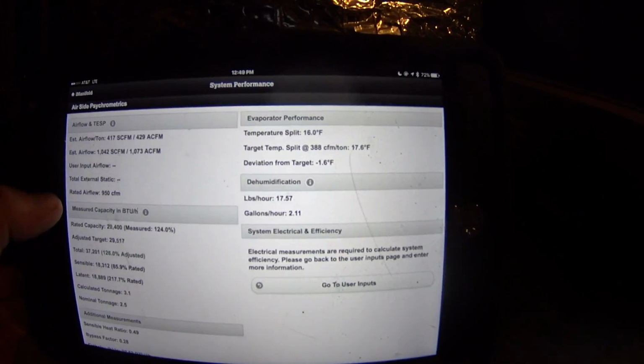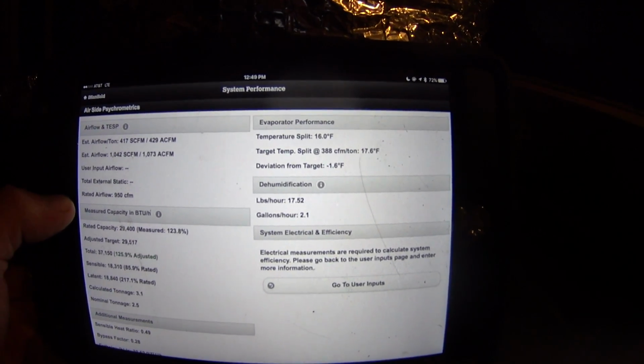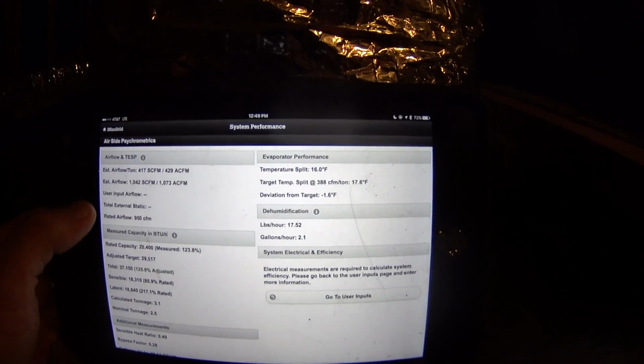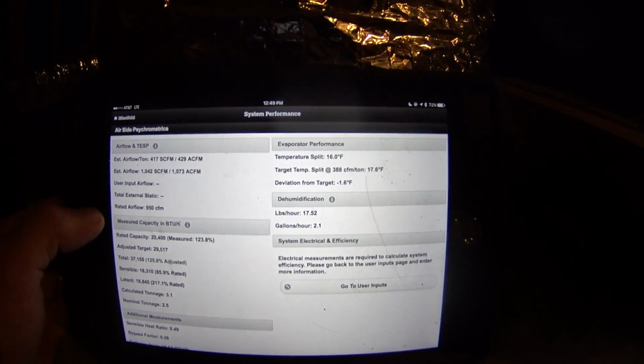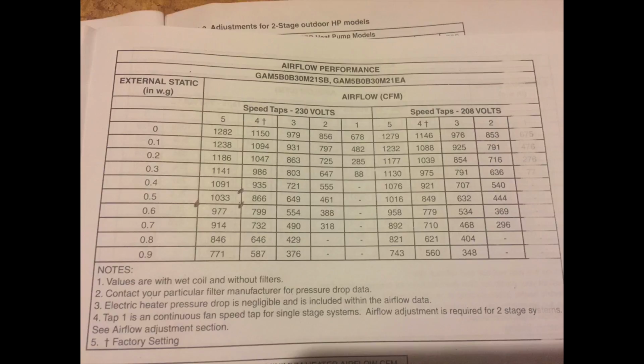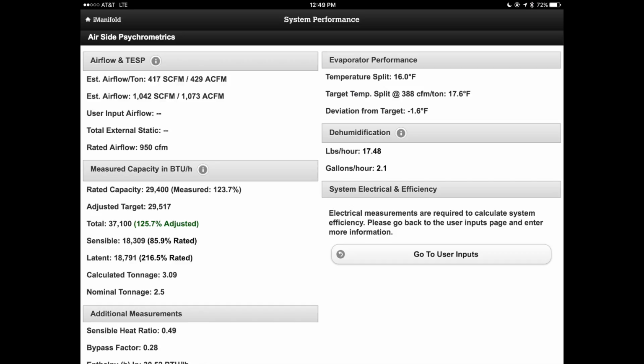So I think I'm going to dig into the blower speed settings and see if I can drop it down just a little. I went to the manual to see what I would need to do to probably hit it with the first try, and it looked like speed tap 4 was going to do the trick. These are the numbers before, these are the numbers after making the blower speed tap adjustment from number 5 to number 4. It's actually interesting to note that the number 4 speed tap was factory setting.